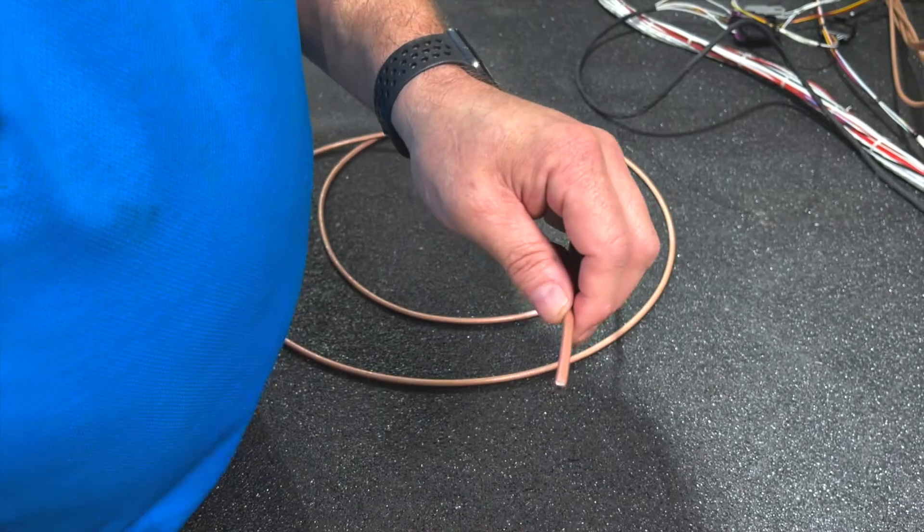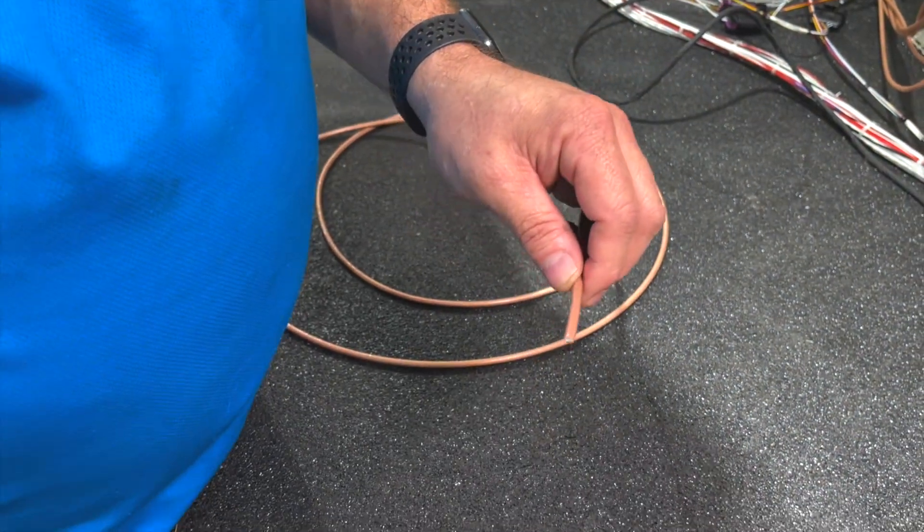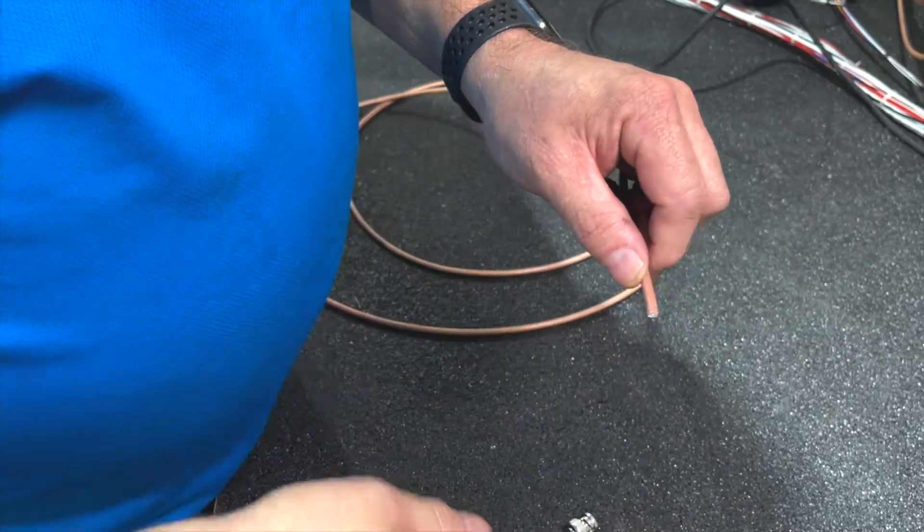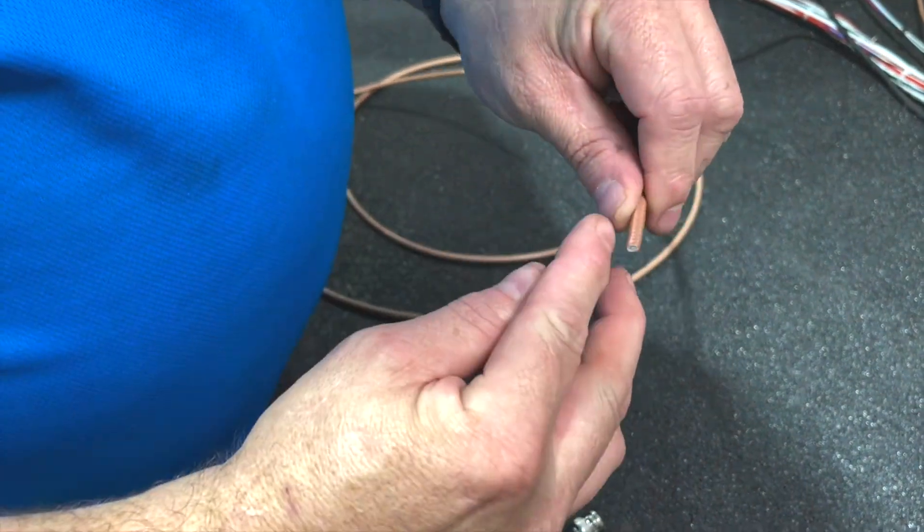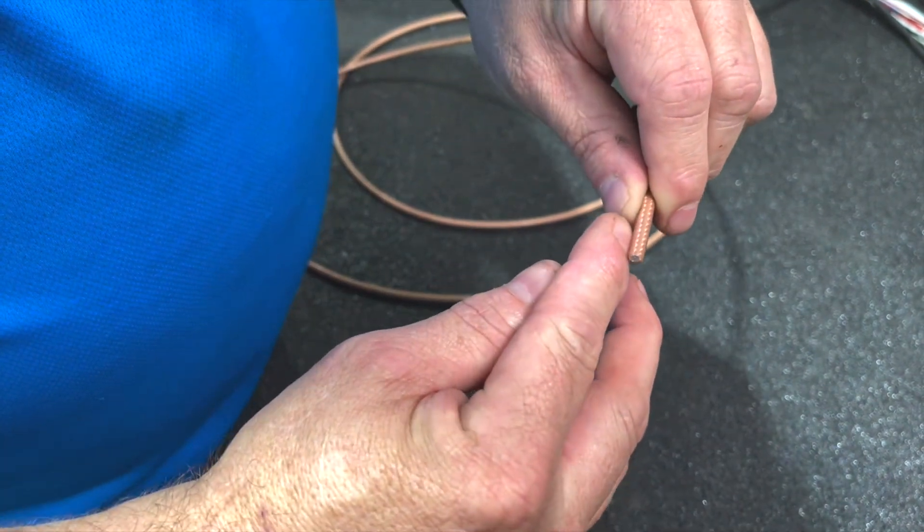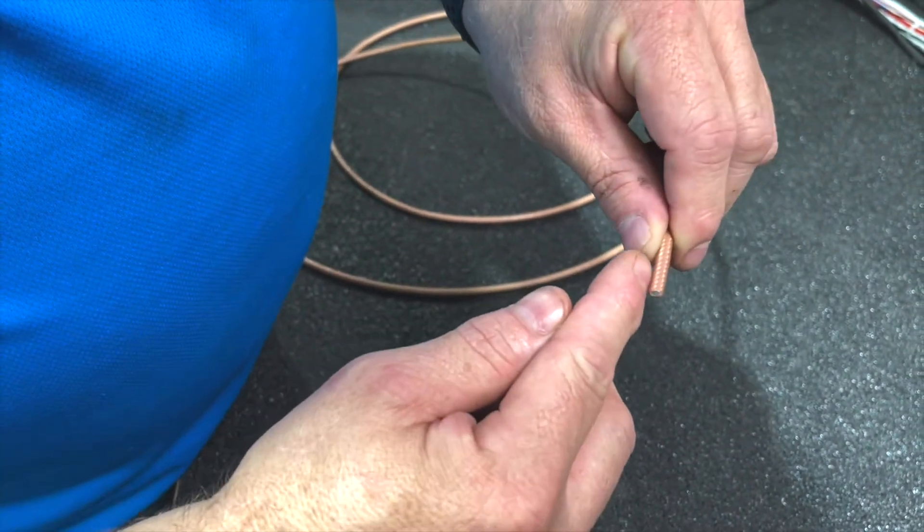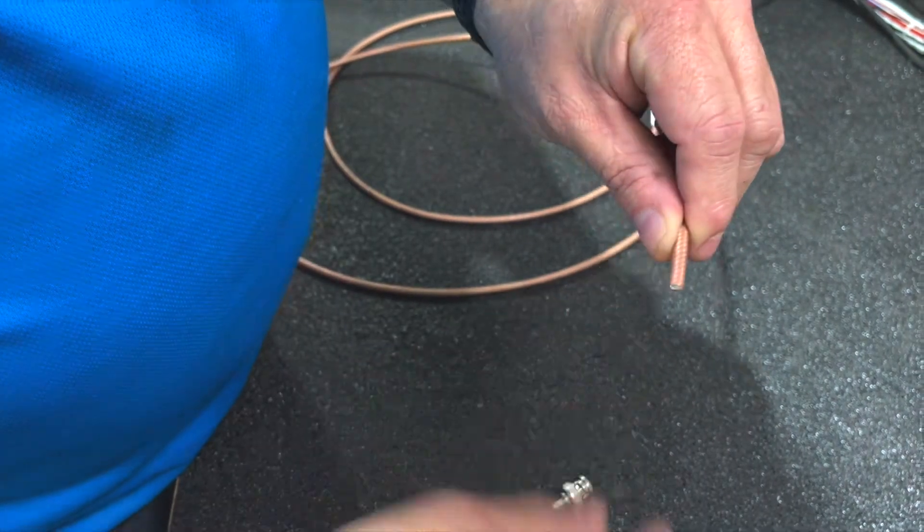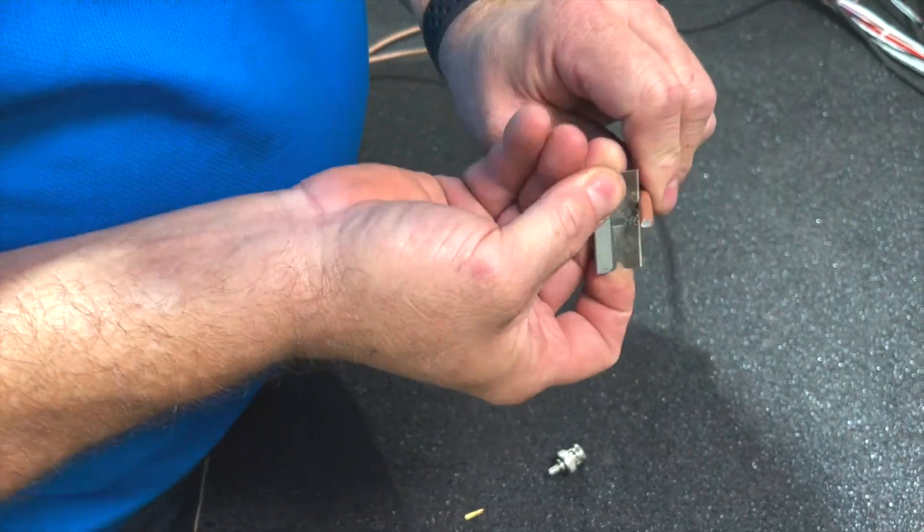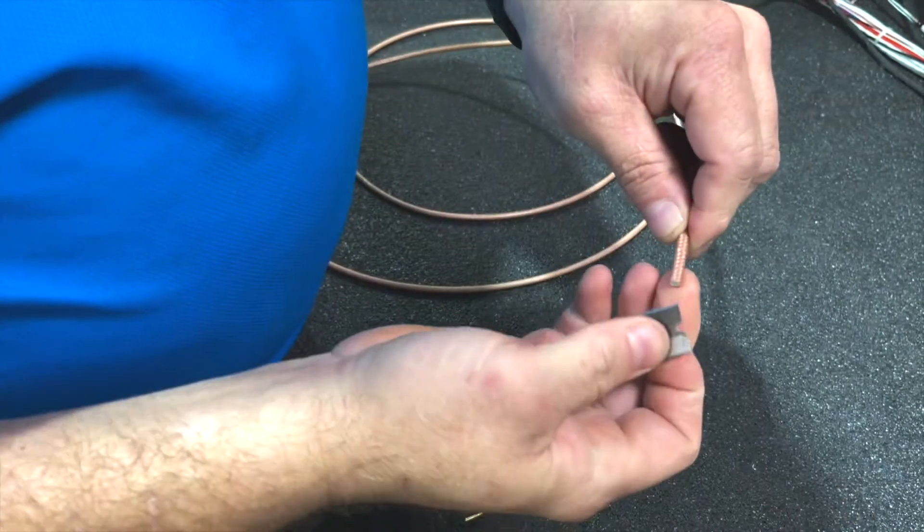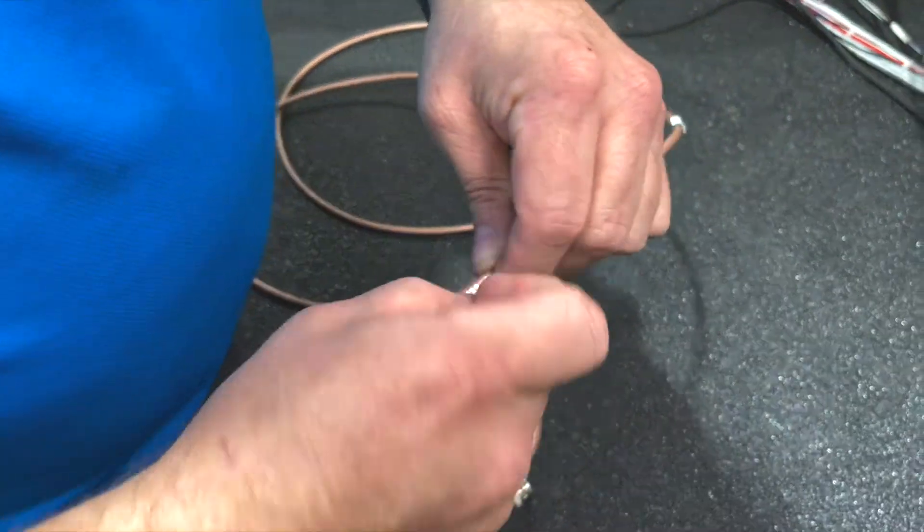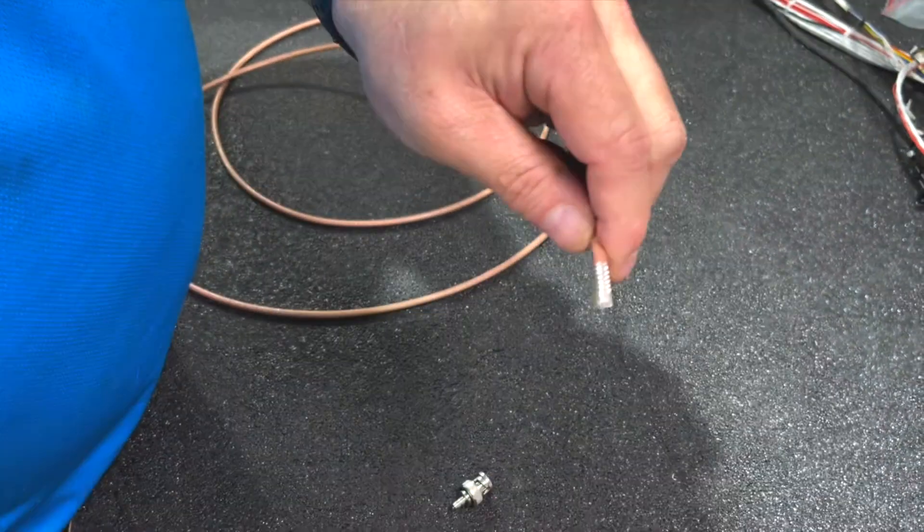All we use is a blade, snips, and a crimper. We just do them all by hand. So we need to strip this back about a half of an inch. I start by putting it to the tip of my nail here, then to my thumb, and that gives me a good reference on where to score this outer jacket. So we'll go ahead and score the outer jacket. Don't go too deep, then we make a slit down the center of it, and then that allows us to peel that jacket right off.